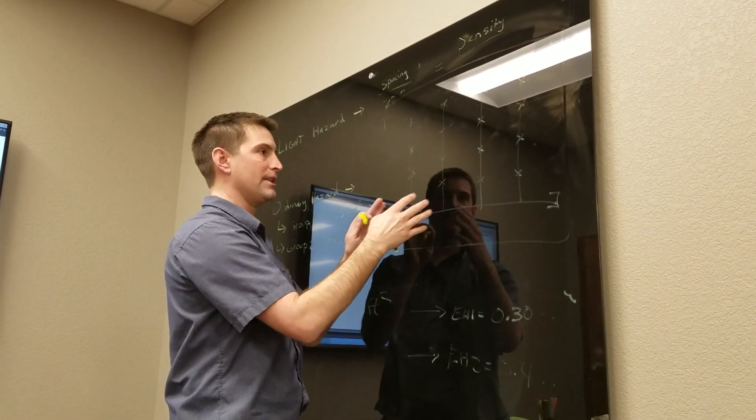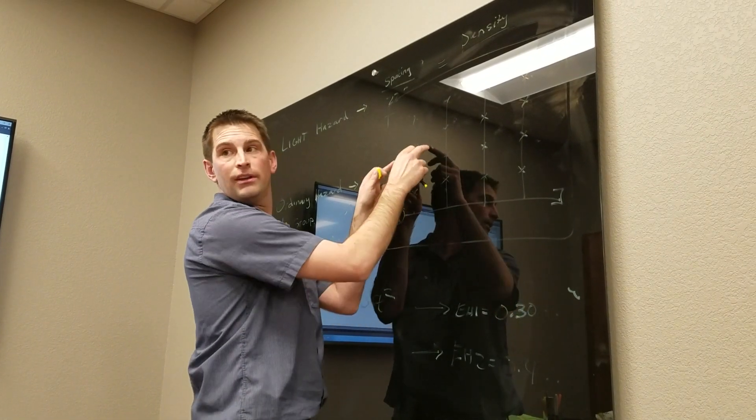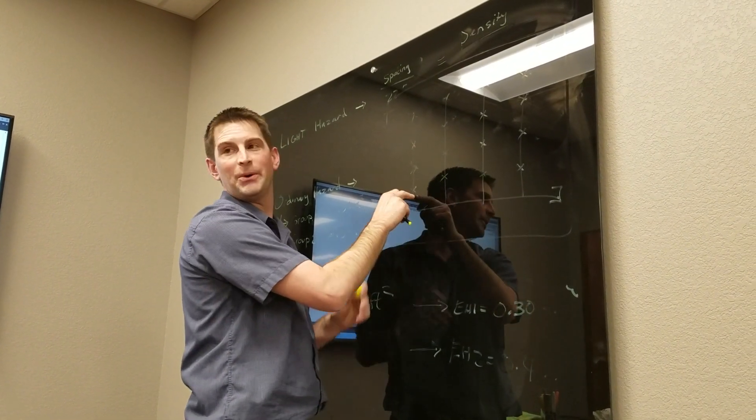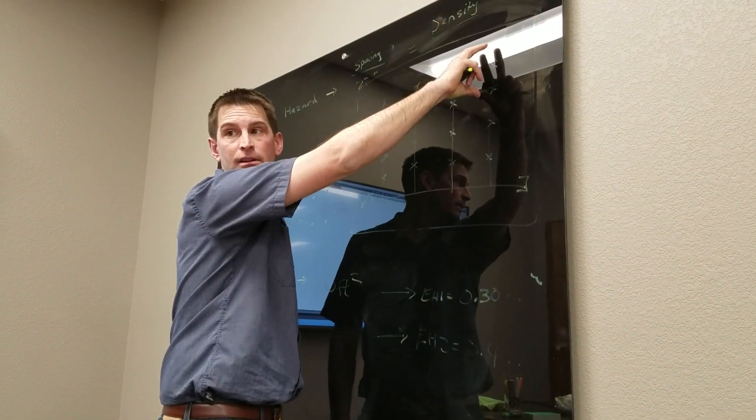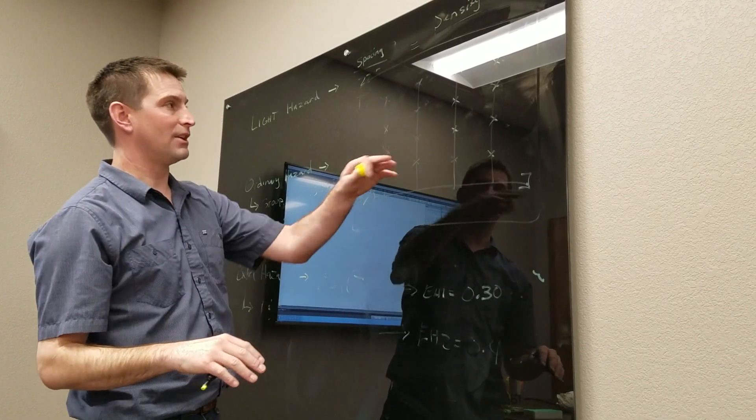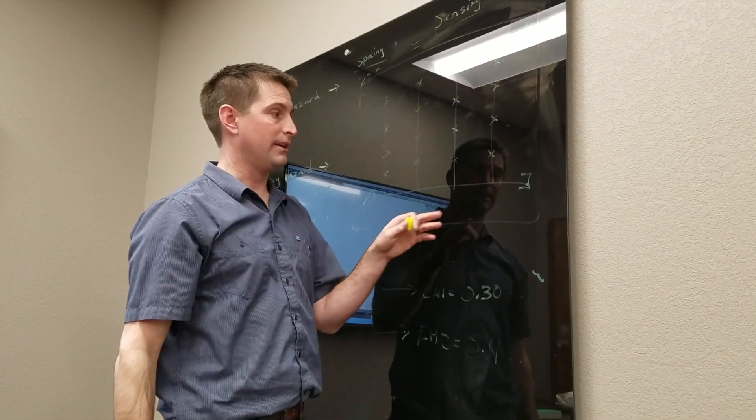If I had this building, this is all light hazard, but they had a tire store right here in the building, well that's probably more demanding even though it's closer to my water supply. But to make it easy, let's say it's all light hazard. This is the furthest place water has to get to, right?